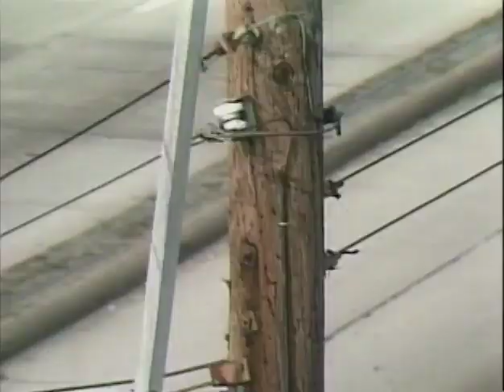Protective grounding is creating an electrical path to ground by installing one or more electrical conductors between the de-energized circuit and the ground. This path can protect you by maintaining the circuit at or near ground potential should the circuit suddenly become energized. Now we'll look at some of the conditions that can cause de-energized lines to become energized unexpectedly and discuss two types of grounds. We'll also go over one method of installing a protective ground.